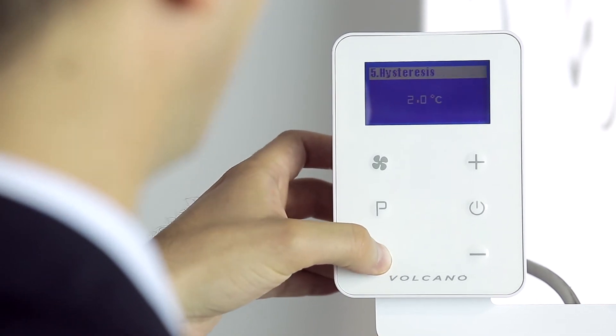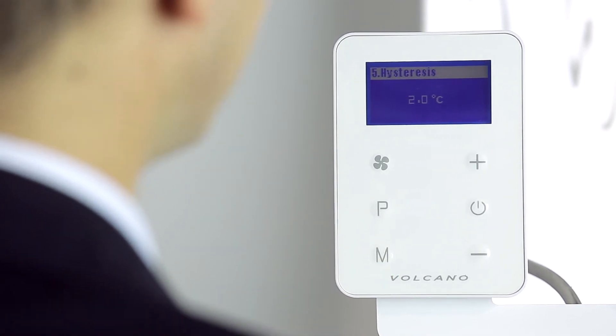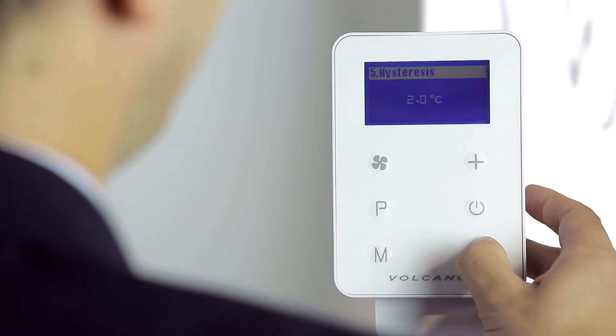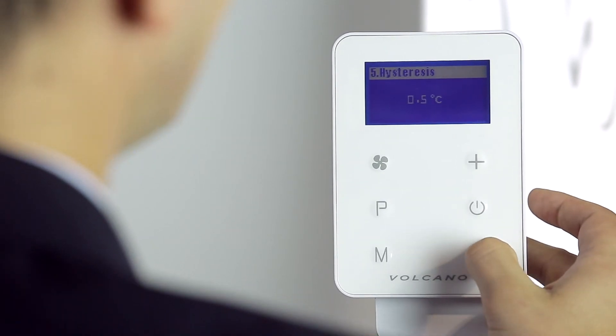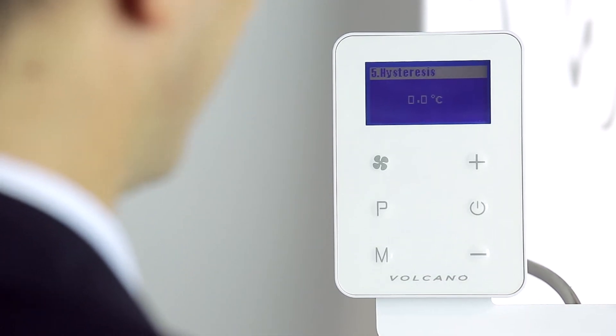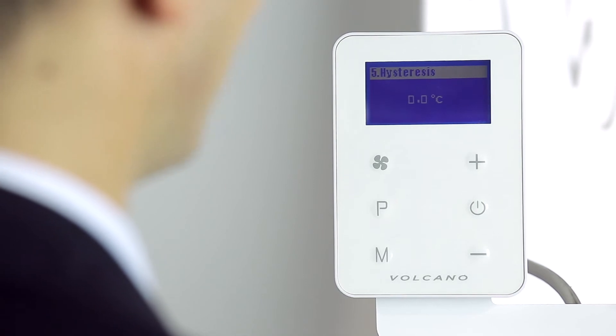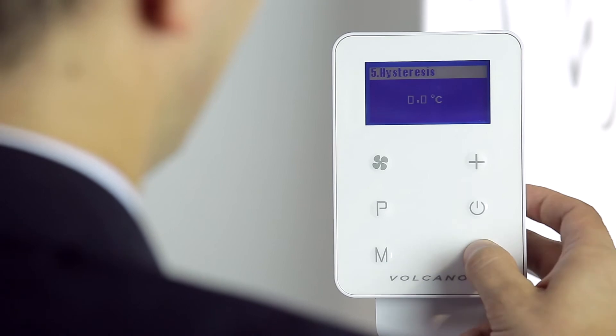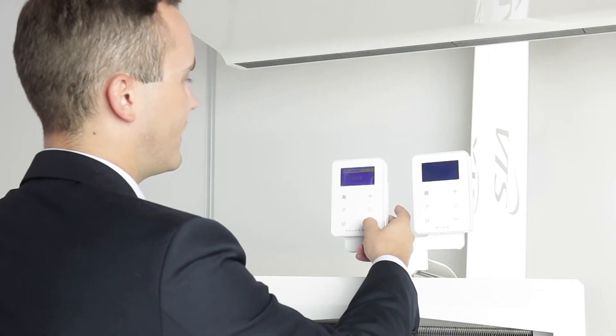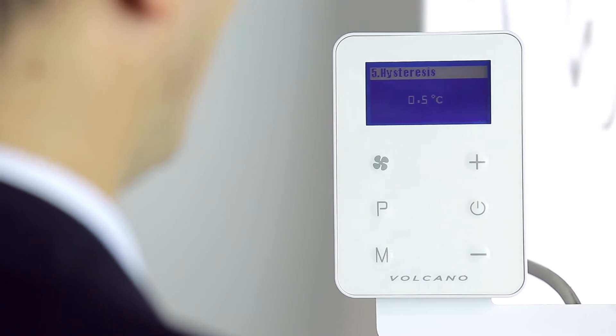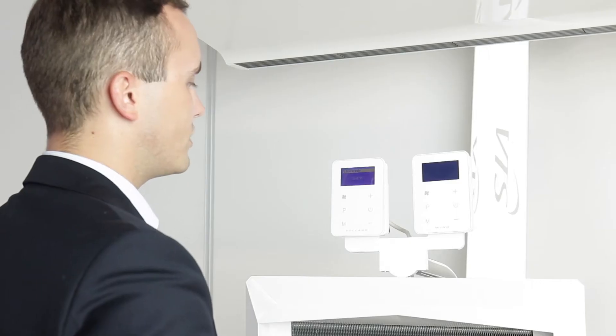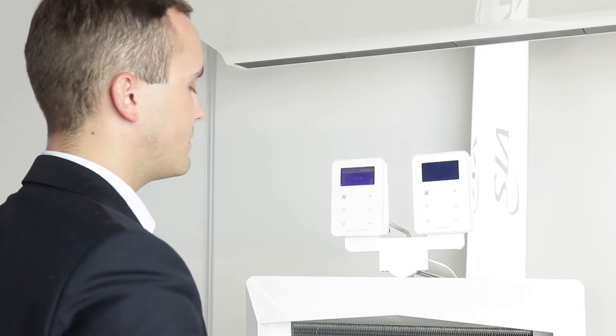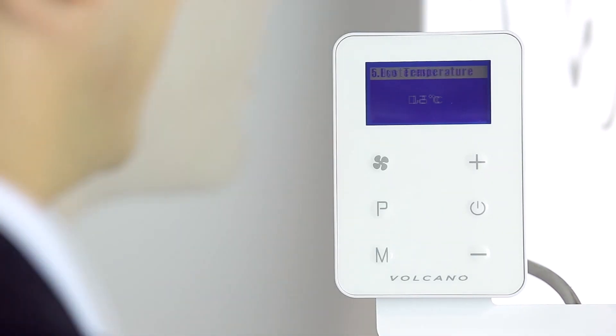Press the M button to move to the differential hysteresis setting. In this setting we determine the difference between the set temperature and the actual temperature in the room that will result in the device switching on. For example, if we had set our hysteresis differential at 0.5 degrees and we have a set temperature of 20 degrees, the device will switch on when the actual room temperature reaches 19.5 degrees.